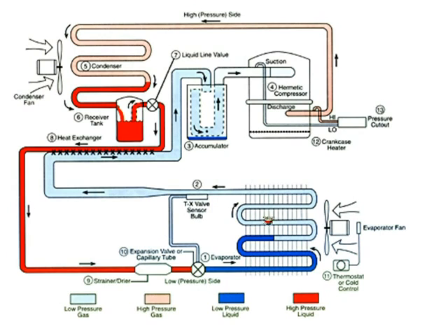So this one's a little bit tougher than this one. But as long as you know about what it should be, most units that work on a 10 SEER, I'm just going to add 20 and I'm good. So 80 degrees, I'm adding 20, so it's 100 degrees right here. Then I come down here where the line sets are coming out, and I take that temperature. Most times it's going to be right around 10, 15 degrees cooler. So 100, 80, 85 degrees or so coming out, and that's your subcooling. You really don't need to hook up any gauges for that either.